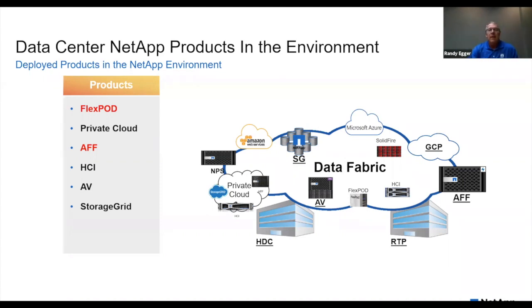Hey, Randy. Yep. I had a question that was in the chat also. What is the industry standard for data center efficiencies? Great question. 10 years ago, the Green Grid came out and said, to have an efficient data center, you're going to be 2.0, which means you're taking twice as much power from the grid to fulfill your IT load, which might be 1 megawatt. So you're pulling in 2 megawatts you're paying for, but you're only using 1 megawatt on the load. Later on, they've identified that a 1.7 PUE is an industry standard. So they're lowering it, and it's going to continue to decrease.